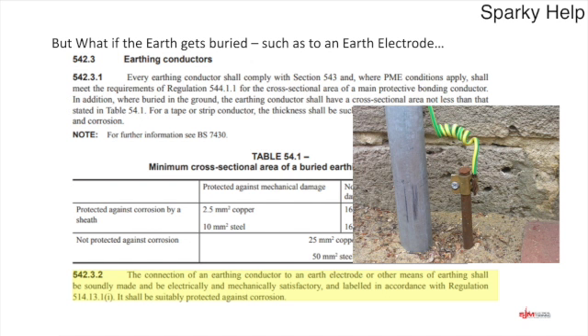Very importantly though is this one here, the very bottom one, because there are many that you see in this picture here where you see earth electrodes that look like this. They're a trip hazard. They're not the best in the world. They probably do the job, probably, but they don't actually meet the regulations. And it says the connection of an earthing conductor to an earth electrode or other means of earthing shall be soundly made and be electrically and mechanically satisfactory and labelled in accordance with regulation 514.13.1. It shall be suitably protected against corrosion. So how many faults are there with that particular one, and how many times have we come across earth electrodes that look like this?